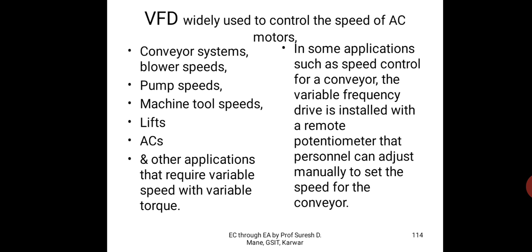So conveyor systems, blower speeds, pump speeds, machine tool speeds, lifts, ACs, they require various speed and variable torque. If you just see this graph, I think here you will get to know it in a very clear way. The top one is the real curve, red color. You have got two axes. X-axis is percentage capacity loading, and Y-axis is the power.